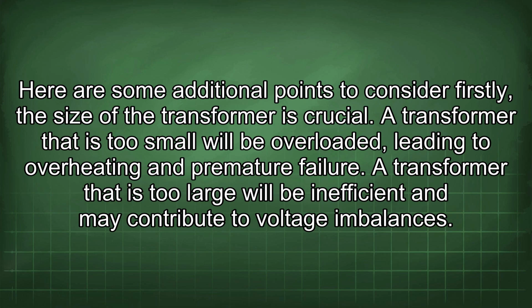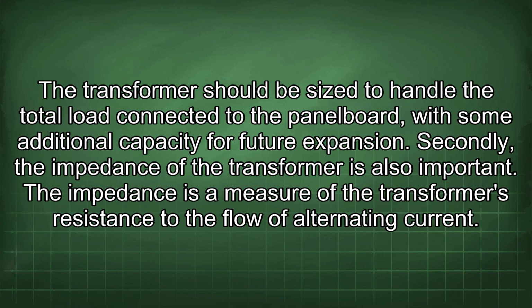Here are some additional points to consider. Firstly, the size of the transformer is crucial. A transformer that is too small will be overloaded, leading to overheating and premature failure. A transformer that is too large will be inefficient and may contribute to voltage imbalances. The transformer should be sized to handle the total load connected to the panel board, with some additional capacity for future expansion.